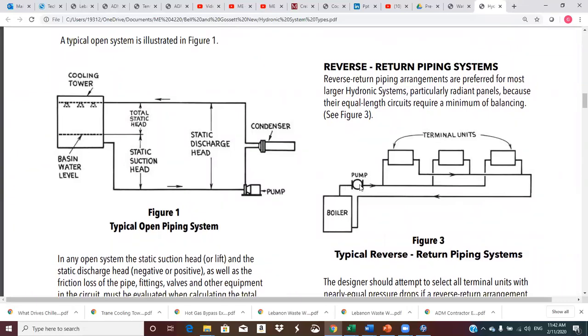So we're coming out of the boiler, and this goes to my shortest supply path, but then I come out and look, so my return then goes all the way down here to the end. Now it has picked up all of the flows, but returning, and then all the way back down here. So what this does is it tends to equalize the length of the flow path considering the supply and the return. So, we have a short path here, but we have a very long path on the return.